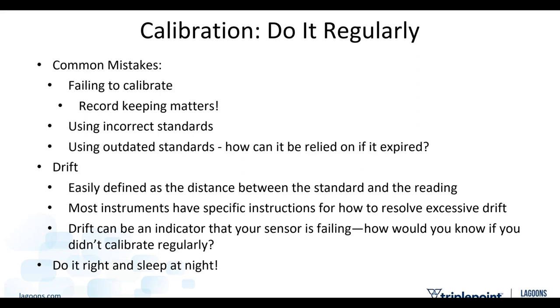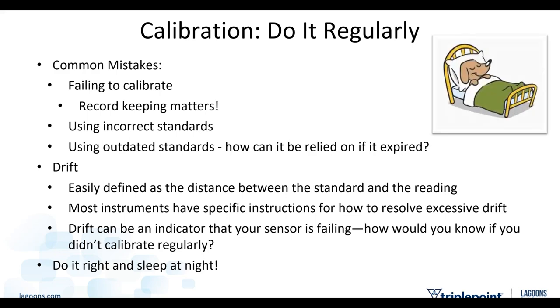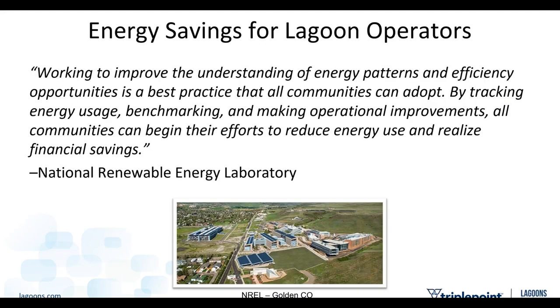You can't even say. And drift, you've heard me say it a couple of times, is easily defined as the distance between the standard and the reading. And most instruments have specific instructions on how you resolve excessive drift. You may need to replace a sensor, there may be a process you follow, or you may have to send it back to the factory. And I encourage you to do your calibration right and sleep at night. There is just no replacement for the peace of mind that comes from saying, I am accurate, and I know that I'm accurate because I calibrate my equipment and I maintain my equipment.